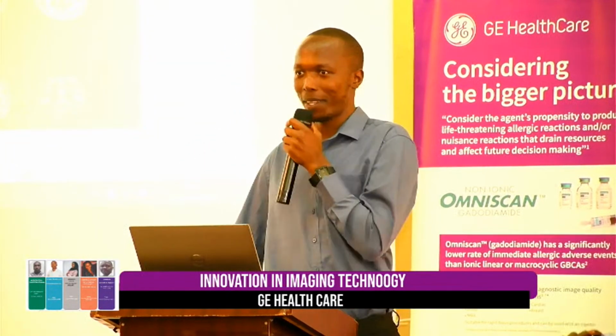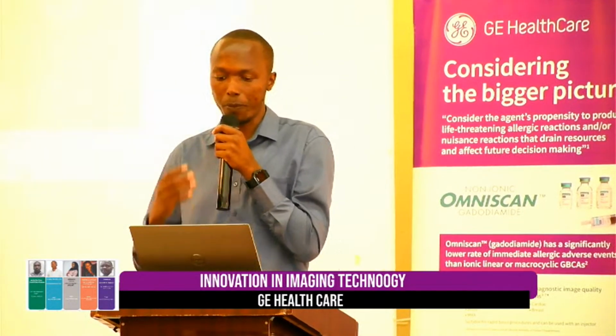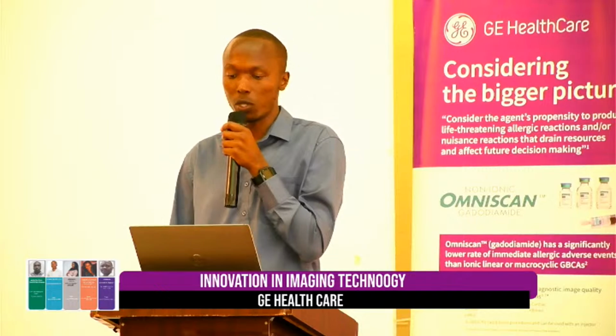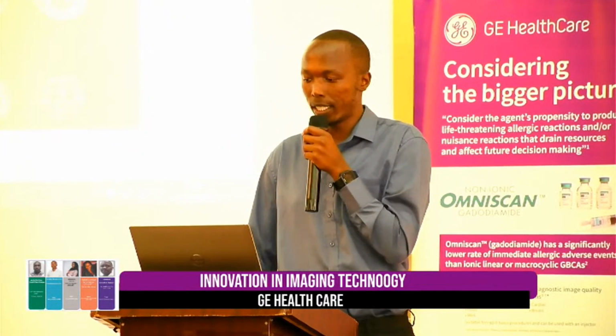Okay, so the next advancement involves synthetic MR imaging. I use the example of killing 2 or 3 birds using one stone. So this is a technique that is able to generate multiple image contrasts using only one acquisition. This technique utilizes a multi-delay, multi-echo, fast spin echo technique. And the signal that we receive will be dependent on the T1, the T2, the proton density, and on the RF of the MR system.